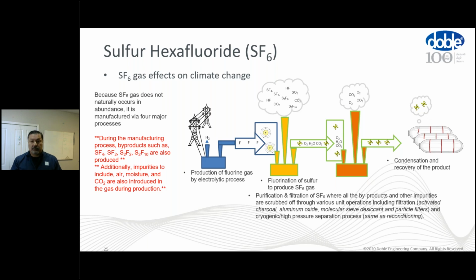And those byproducts are released as part of the scrubbing process, where we use activated charcoal or aluminum oxide, molecular sieve desiccant, and particle filters to scrub out those byproducts. And then a cryogenic and a high pressure separation process, much like what we do in reconditioning, is done. At that point, we scrub out all those bad contaminants. We also reduce the other air and other CO2 contaminants that are in the SF6 to produce pure SF6, which is then consolidated, put in the tanks, and then introduced into the supply chain. And again, that last piece, that separation process, is also the process for reconditioning of SF6 gas, which I'll touch on a little bit later.